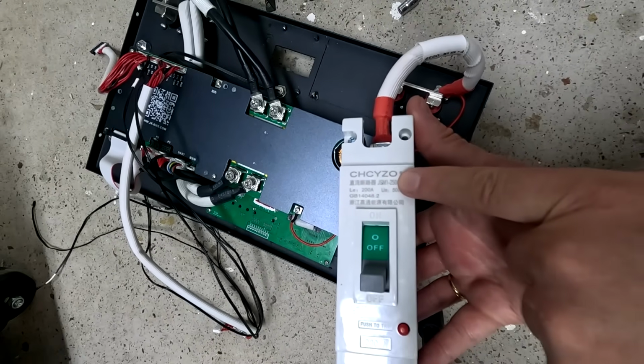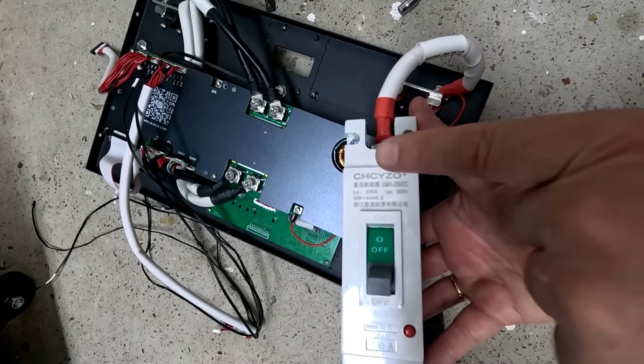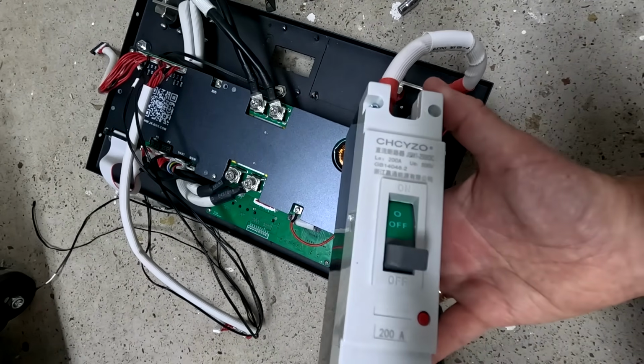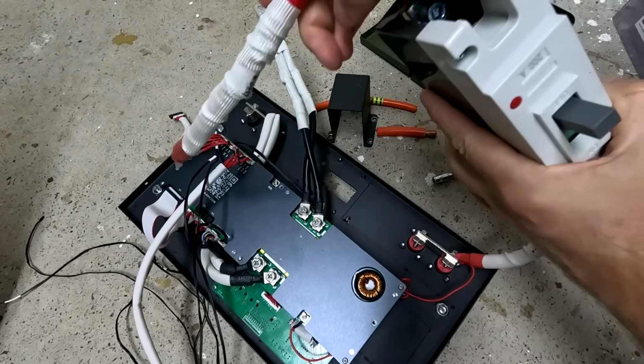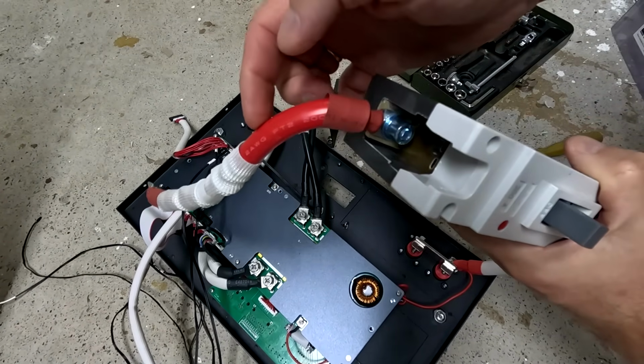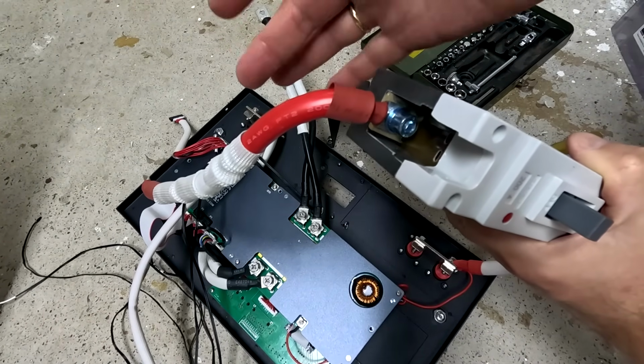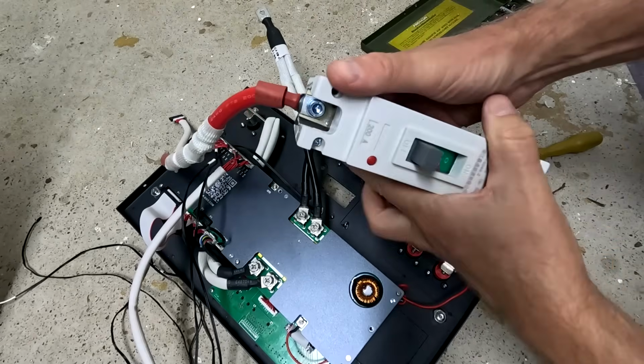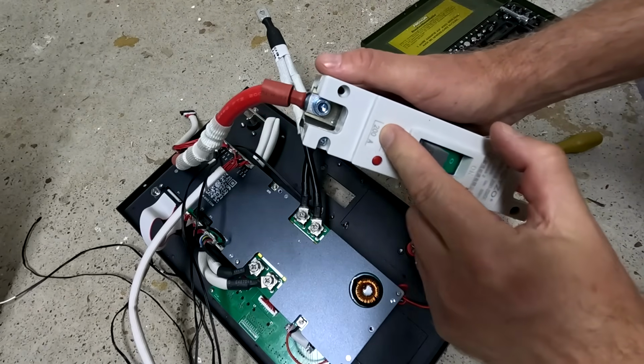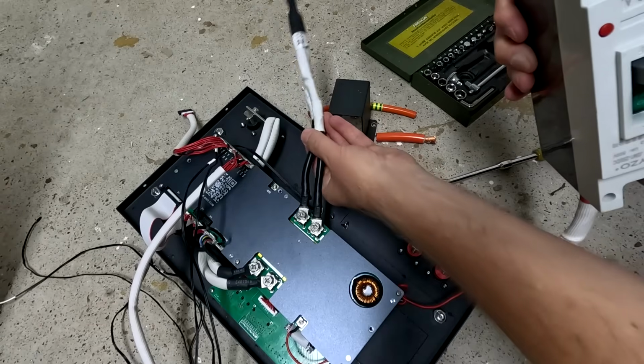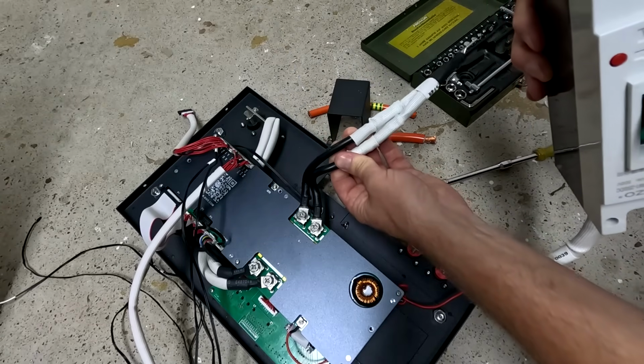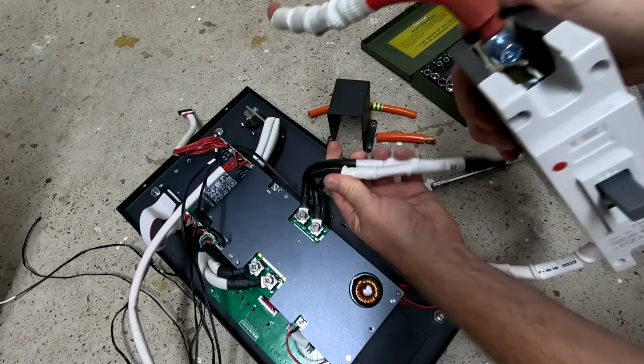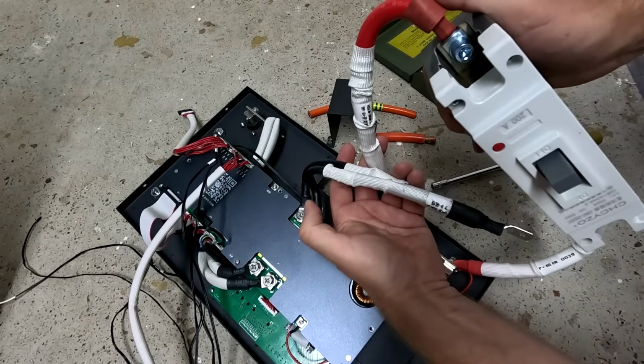So I would highly recommend to install a Class T fuse inside this battery box here. Yeah, well, and then we've got all this cabling. This is a 35 millimeter cable rated for 120, 130 amps maybe. And we've got a 200 amp circuit breaker, so this does not fit together. And the same here with these ones. 2 times 16 square millimeter is roughly the same size as the red one here.